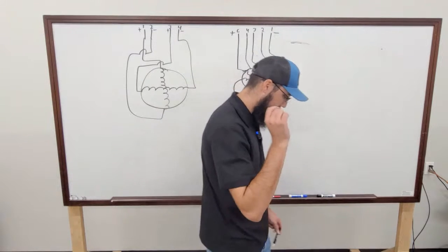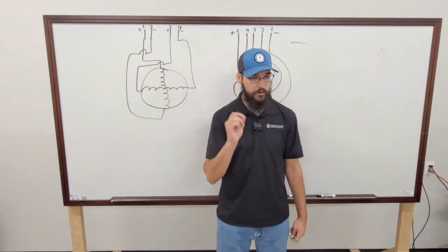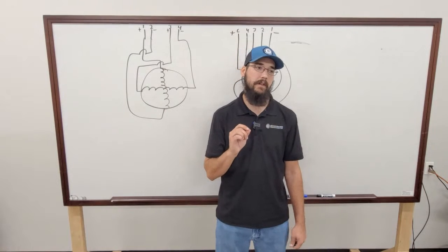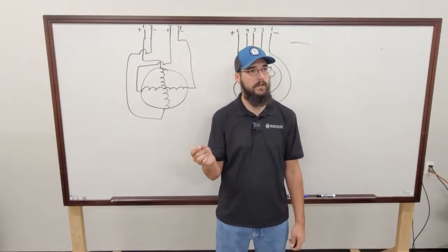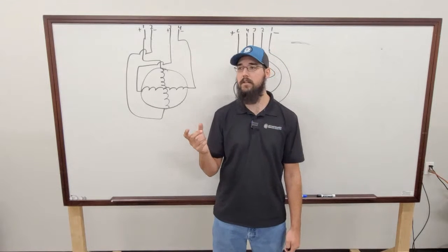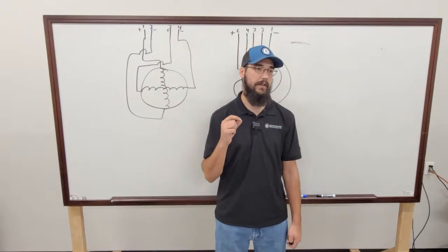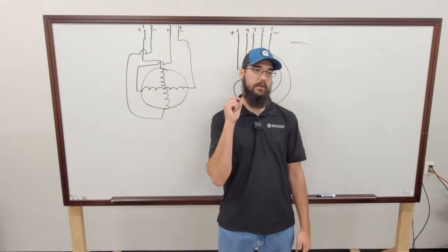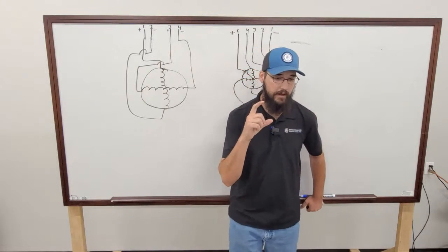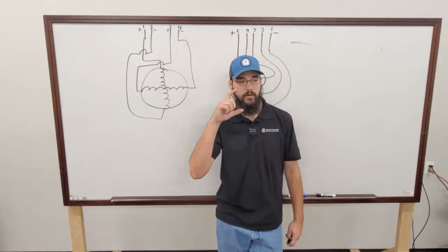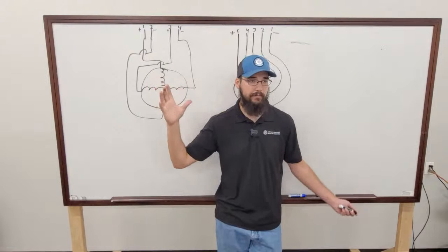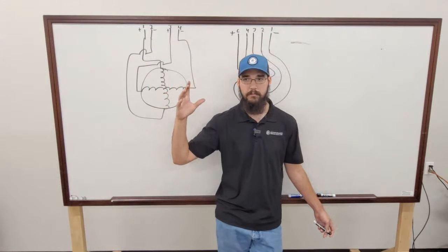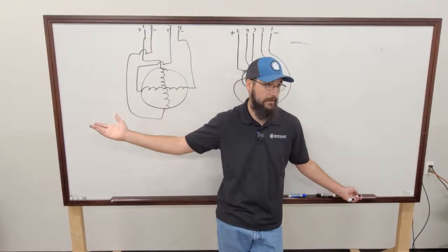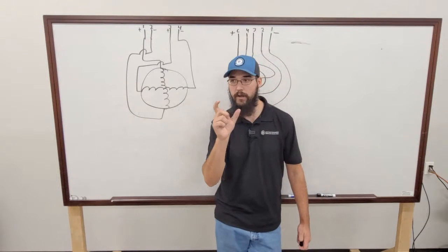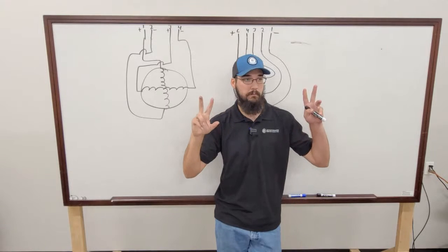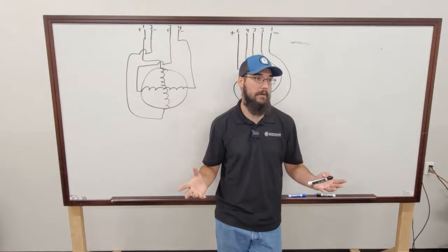Flow sensors. One critical thing I wanted to point out with those: there are a few different styles. The most common would be the thermal dispersion, I think is the term for it. Basically, it's got a little heated diode in there, and it's calibrated to know that if that diode is reading X amount of temperature, then I am or am not flowing water, essentially. A lot of times they'll have little flow LED indicators where it'll give you some sort of metered reading. So just bear that in mind.